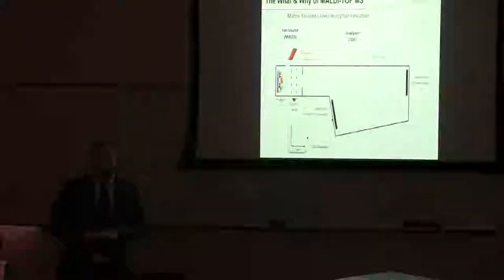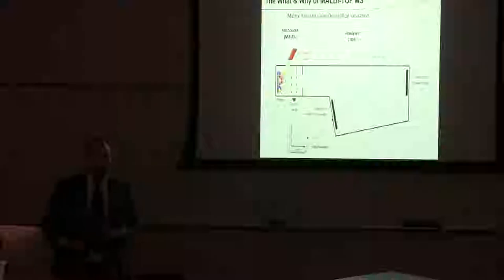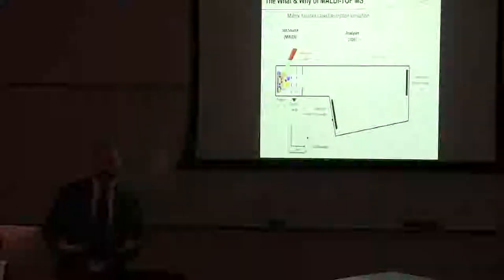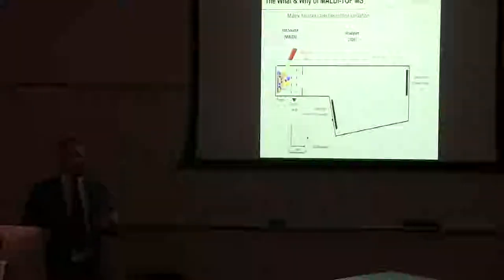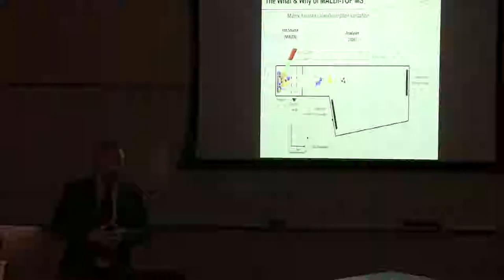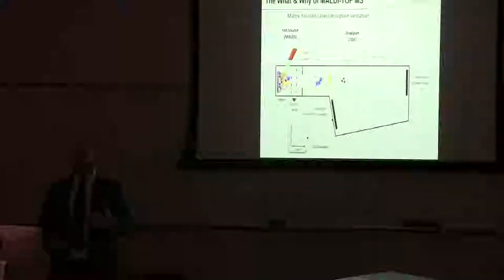And so then following loading the plate into the instrument, you need to form the ion. So in MALDI, you're using a laser that is a wavelength that is close to the maximum absorbance of the matrix. The laser energy then is transferred by the matrix to the sample to induce ionization. After which the analytes are going to separate based on their M over Z through the time of flight.